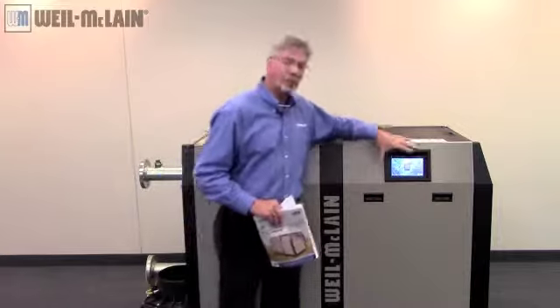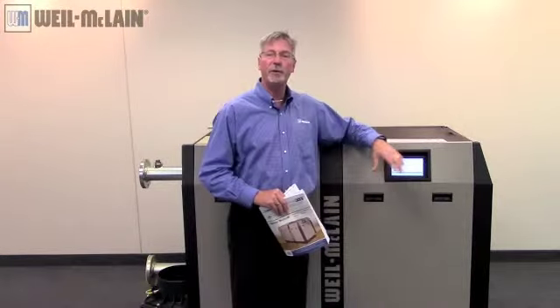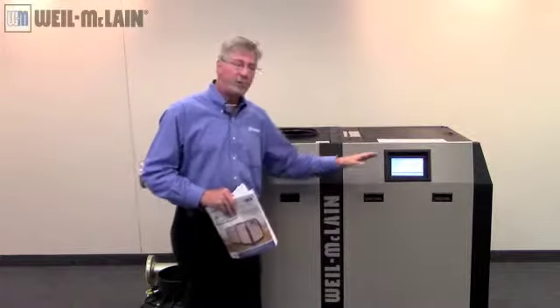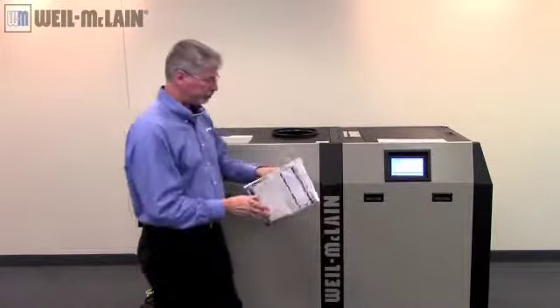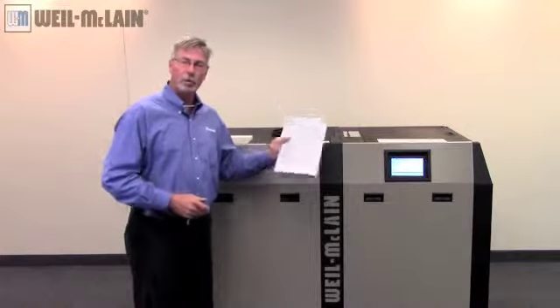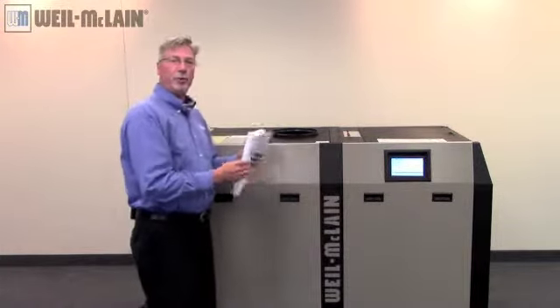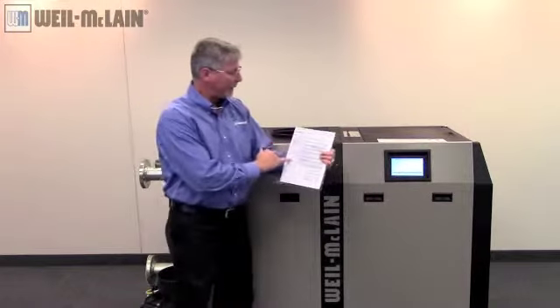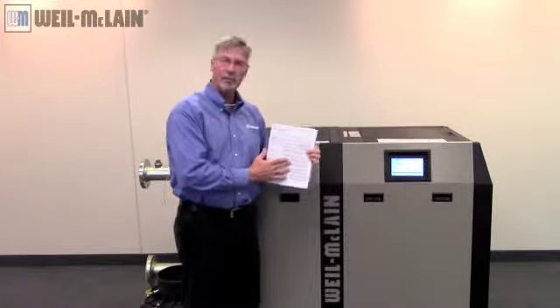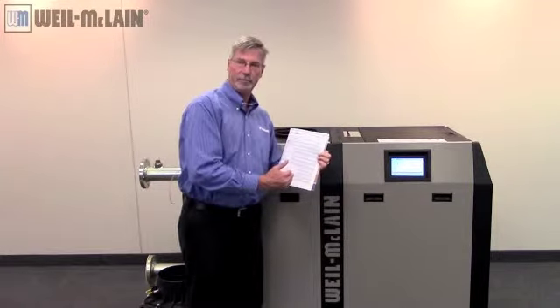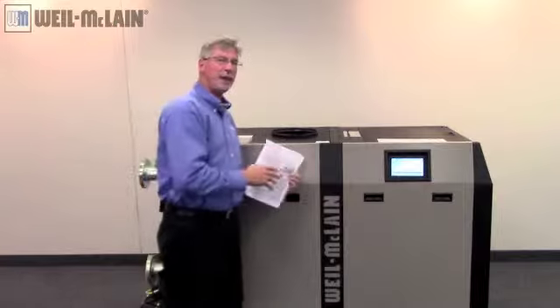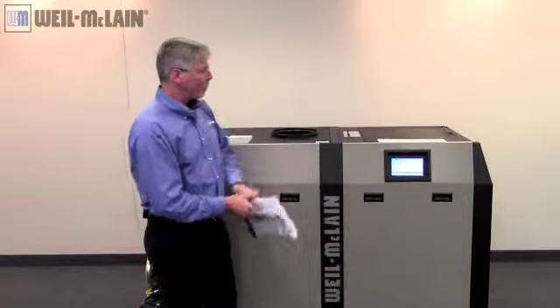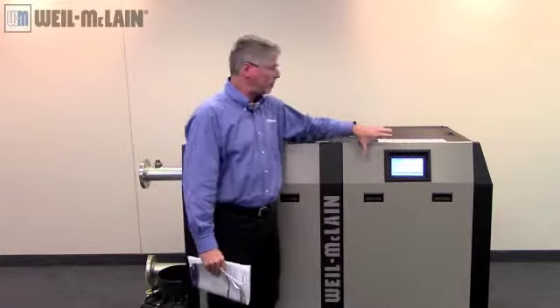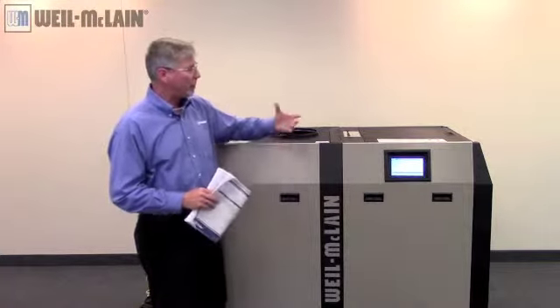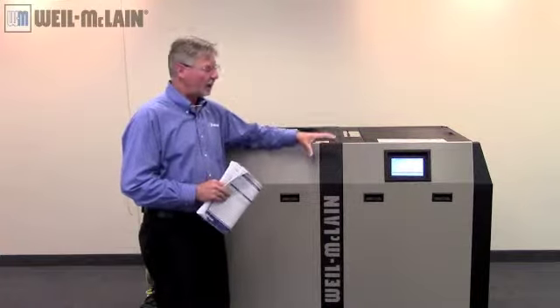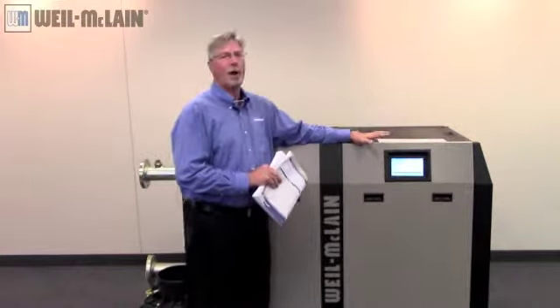Now, take a look at your temperature screens. When you go right into your configuration screen, remember, live time, we see the temperatures right on the screen, what's going on. Now, in your manual, it gives you step-by-step procedures in the matrix: what your display is, what the condition is, what the diagnostics are, and what the corrective action is. If you follow those procedures step by step, you should be able to get to that solution. Now, with the temperature sensors the way they are, you can do a couple of things. In the manual, we also have a graph showing you the resistance of the sensor. So if you suspect the sensor being the issue or the problem, well, that's good.